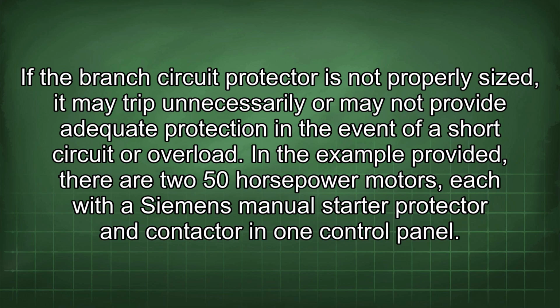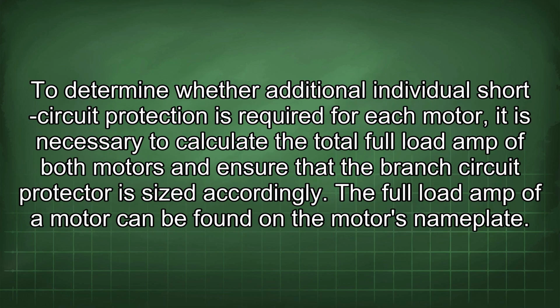In the example provided, there are two 50 horsepower motors, each with a Siemens manual starter protector and contactor in one control panel. To determine whether additional individual short circuit protection is required for each motor, it is necessary to calculate the total full load amp of both motors and ensure that the branch circuit protector is sized accordingly.